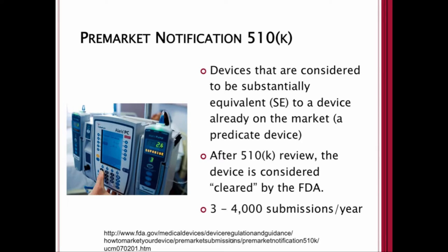Pre-market notification through the 510K process applies to devices considered substantially equivalent to a device already on the market — a predicate device. After 510K review, the device is considered cleared by the FDA. The FDA receives roughly 3,000 to 4,000 submissions through the 510K process per year.